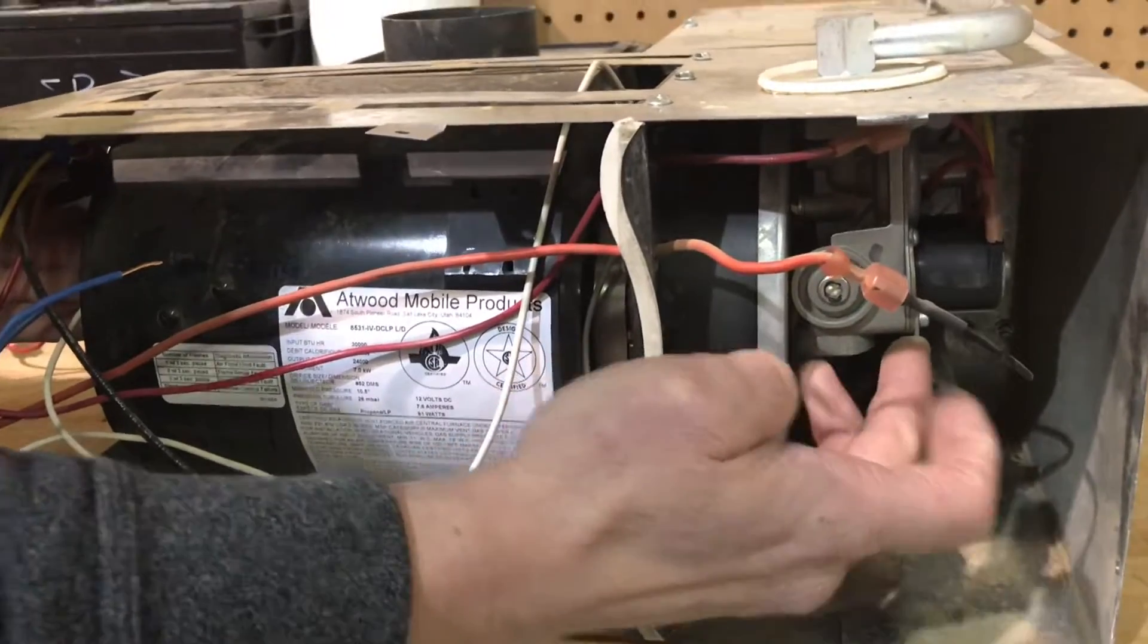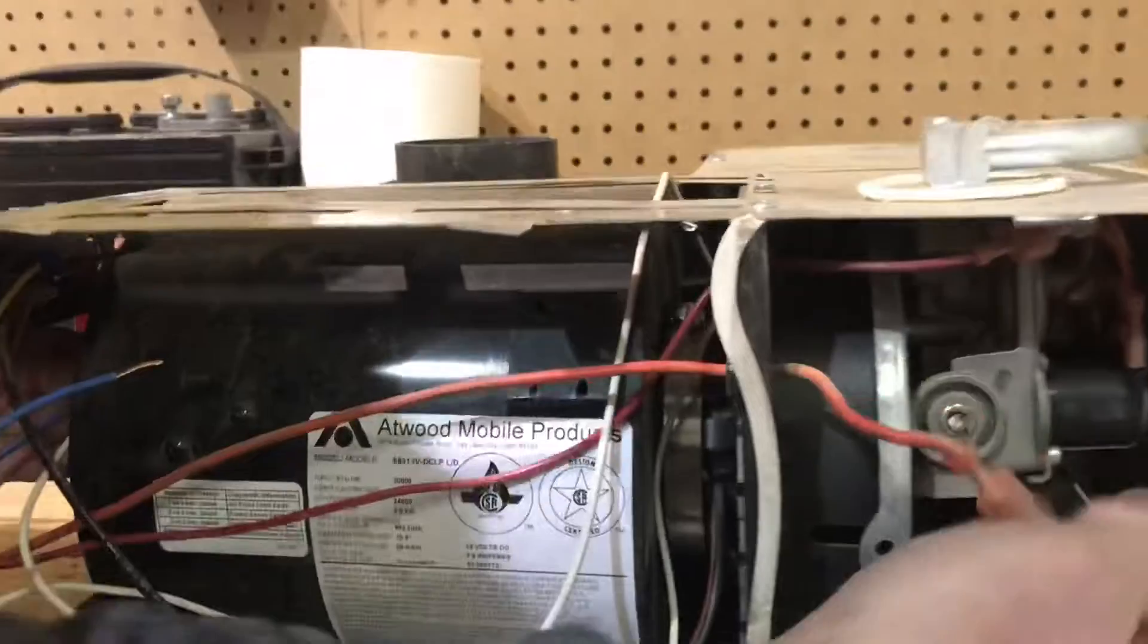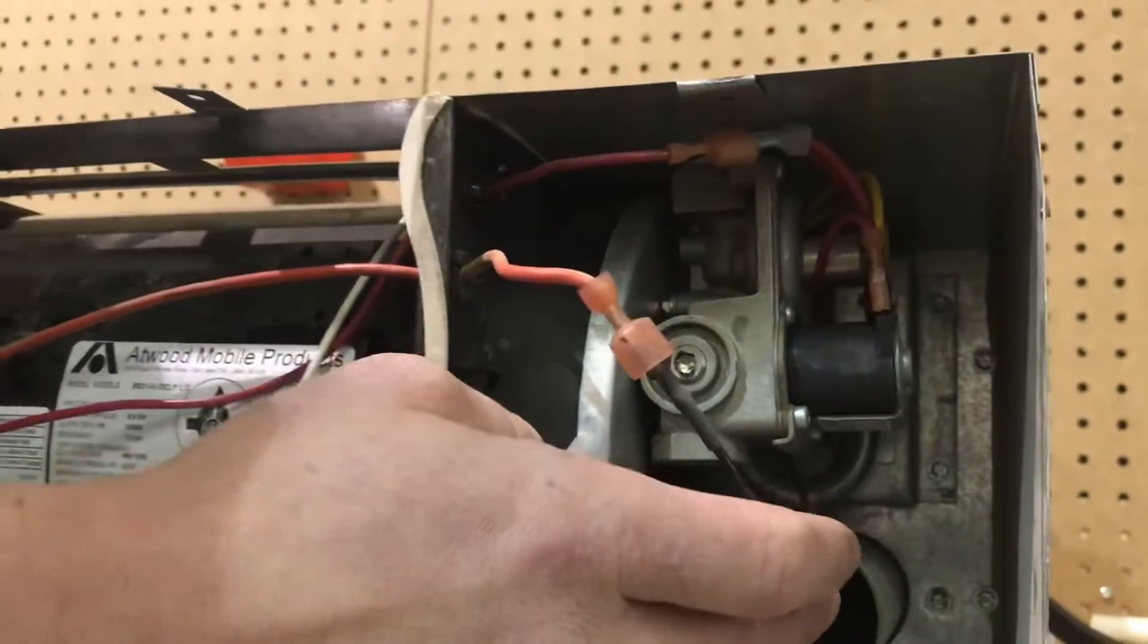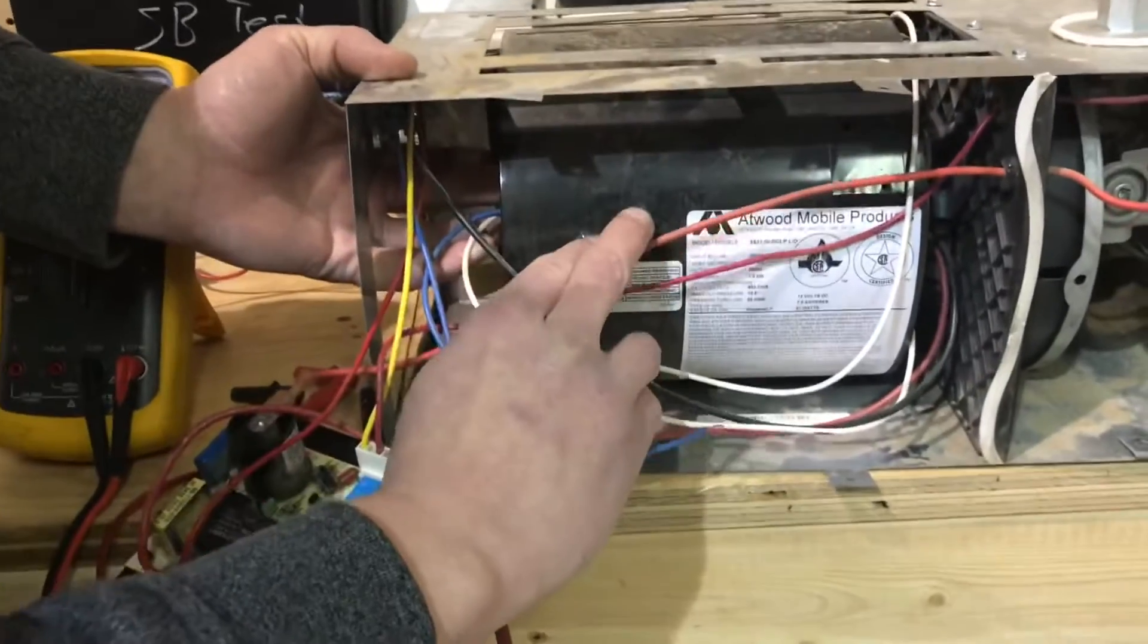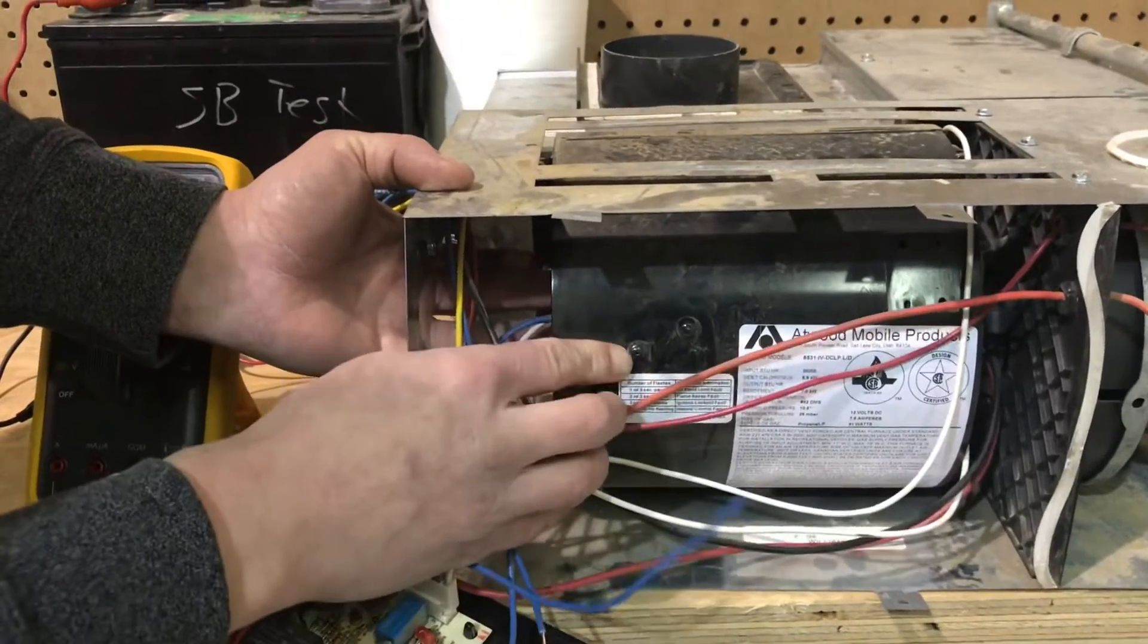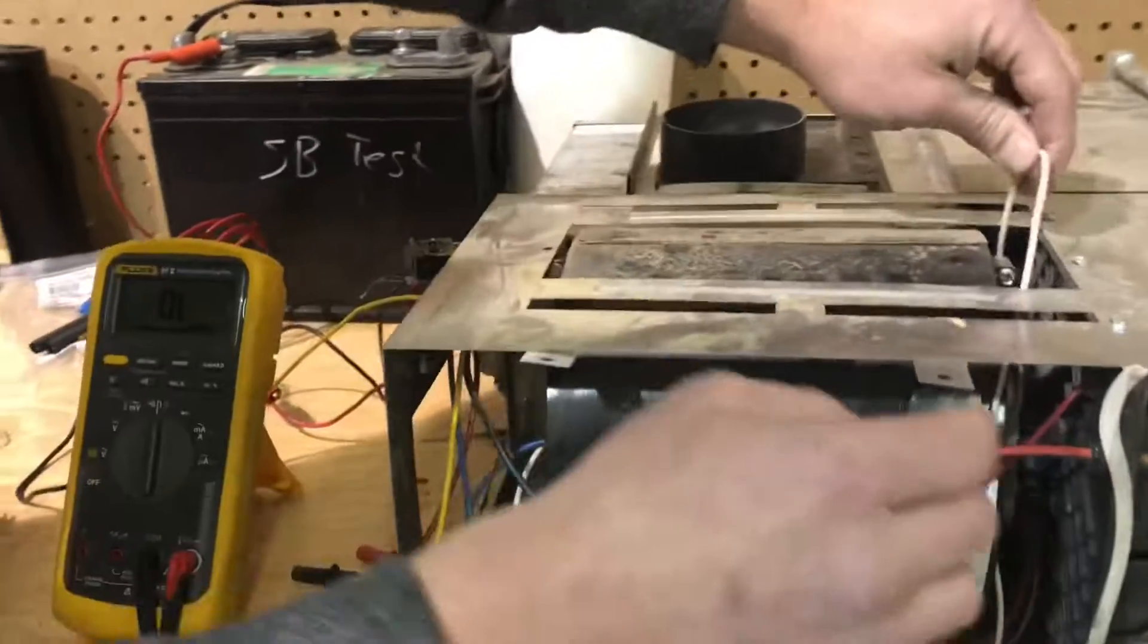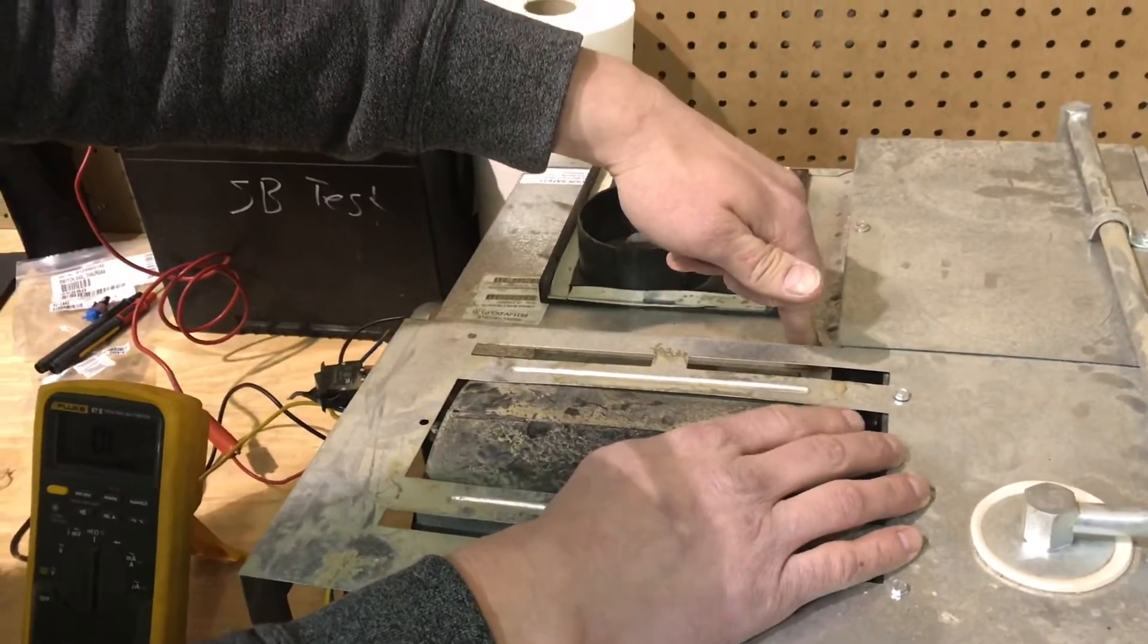There is the gas valve. This lead here leads to the igniter which is tucked up back in there with the gas burner. That is tucked in behind. In this shroud itself, behind these two little dimples here, is a sail switch. Then behind that, attached to these wires here on these Atwoods, is a high limit switch.